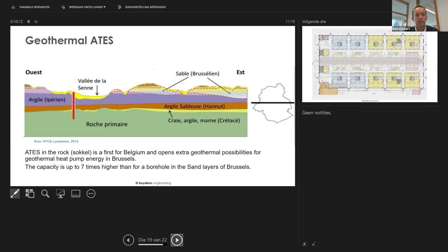A classic solution, the red borehole we see here, normally goes to 70-75 meters. What we did here is drill a bit deeper until we hit the rock of Brussels, added the pipe, cemented the hole, and continued drilling up to 150 meters into the rock. This gives a capacity up to 7 times higher than a classical sand layer system in Brussels, allowing such big buildings to use geothermal energy and heat pumps.